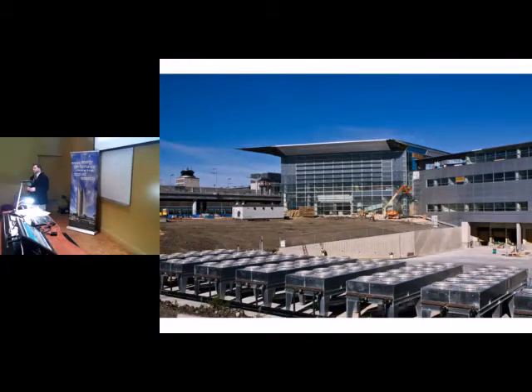So what that allows the building to do is to self-heat and self-cool if necessary. So for example, if you have a data center, we've got a large rack of computers making heat. That heat can be extracted from that space, put onto this energy bus, and then moved over to a space where, say, you might need heating for another reason. It's cold in that space. So we effectively move around approximately 1,500 tons of cooling within the building across this loop. What we do also have on the outside, if there's an excess of energy in the building, say in the summertime, we have 8 very, very large fluid coolers out here to dissipate that energy to the outside. So that's why you're seeing these substantial pieces of equipment when you drive up and look out the window.